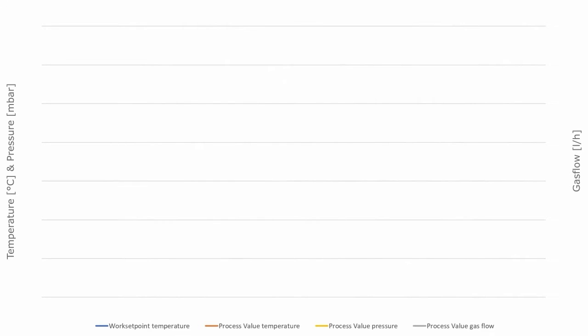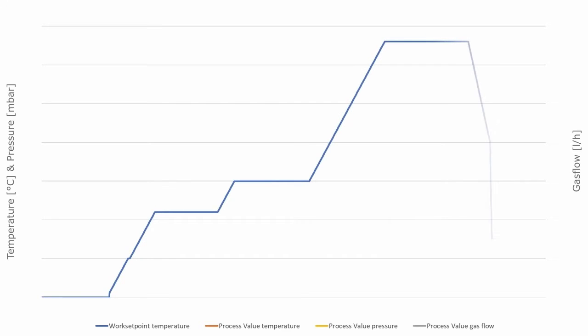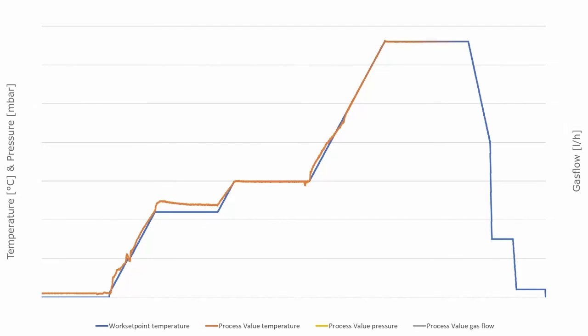The program is configured to run through both process stages: thermal debinding up to 600 degrees C, followed by sintering at 1380 degrees C. The progress is clearly shown in a diagram, with the program working set point represented by the blue line and the actual measured process value temperature represented by the orange line.